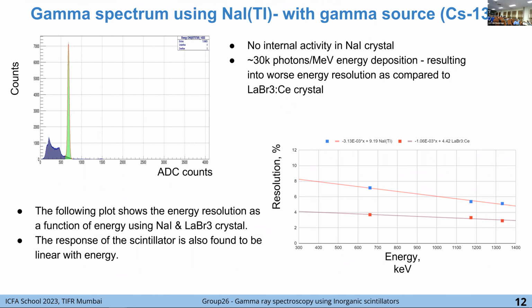So sodium iodide doesn't have any internal radioactivity. That's why we don't have any background without our isotopes. This is a figure for sodium iodide also. Here you can see the photoelectric peak, which is the peak of absorption of the energy of the gamma ray. Here is the Compton scattering peak. And on the red picture, you can see a comparison of our resolutions for the two types of crystals, lanthanum bromide and sodium iodide. Sodium iodide has a lower output signal, which leads to a resolution of about 6-7%.